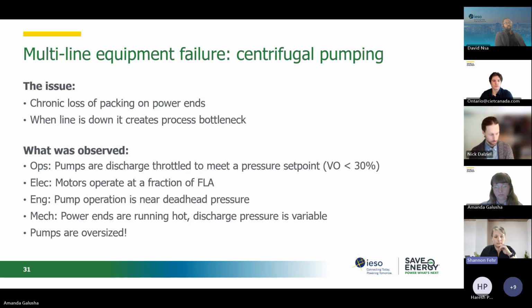The electrical folks had checked the motor load just to confirm the operation of these pumps, to find out that they were operating at a fraction of their full load amps, which means they're not really moving water. Engineering, when you check with them, they always pull the pump curve out, and it becomes clear in a hurry that these types of pumps don't operate well at deadhead pressure, and that's where they were operating. And then the mechanical team can tell you things like maybe the equipment's running hot, and you can feel that in the field. A real telltale sign is to look at the discharge pressure gauge. If the pressure gauge is highly variable, you have some cavitation in this pump. It's easy to conclude in this particular case that the pumps were oversized. And this is a group effort to get to this point.